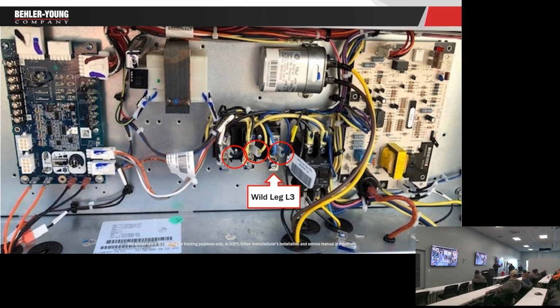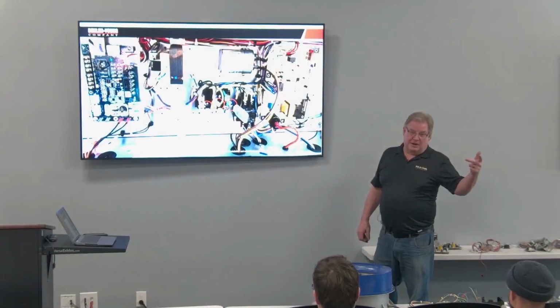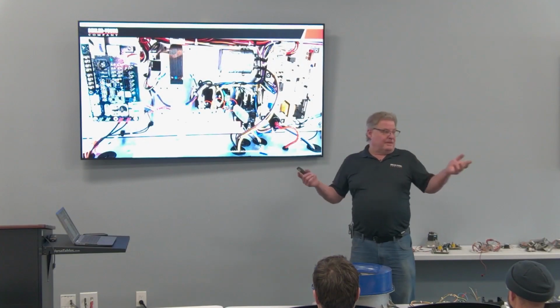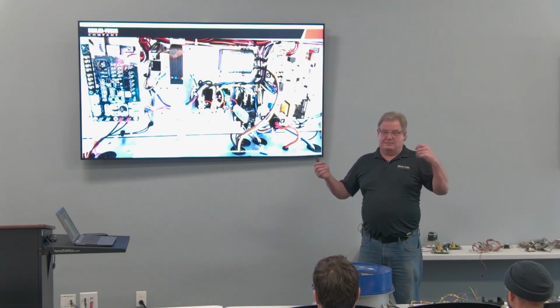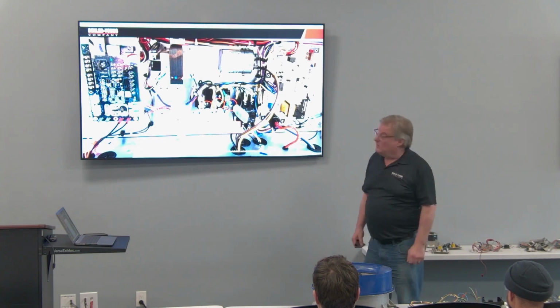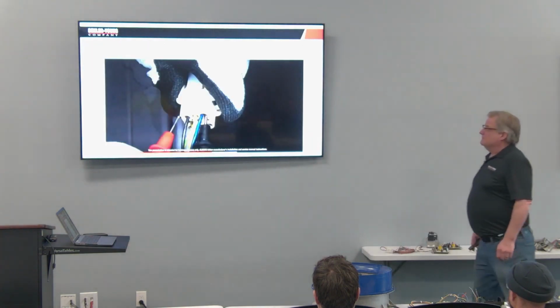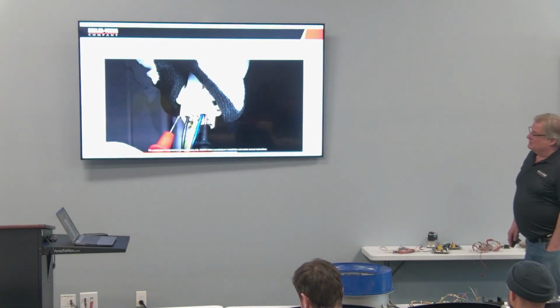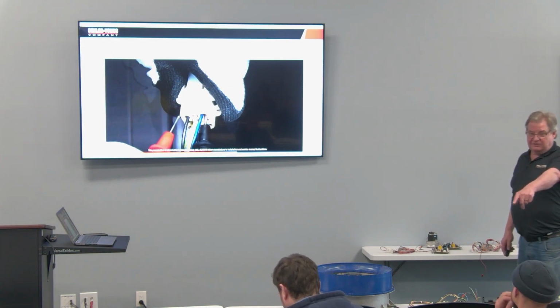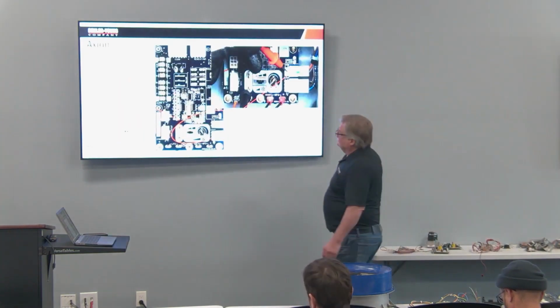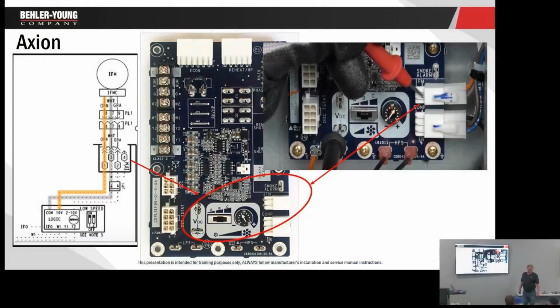Transformer, red. The common is brown. So if I'm trying to pick up 24 volts anywhere, I find brown and red wires, 24 volts. First of all, L1, L2, L3, I have power at the motor because I have had damaged connectors where it doesn't carry through. Now, the way this thing works, I want everybody to be clear on this.